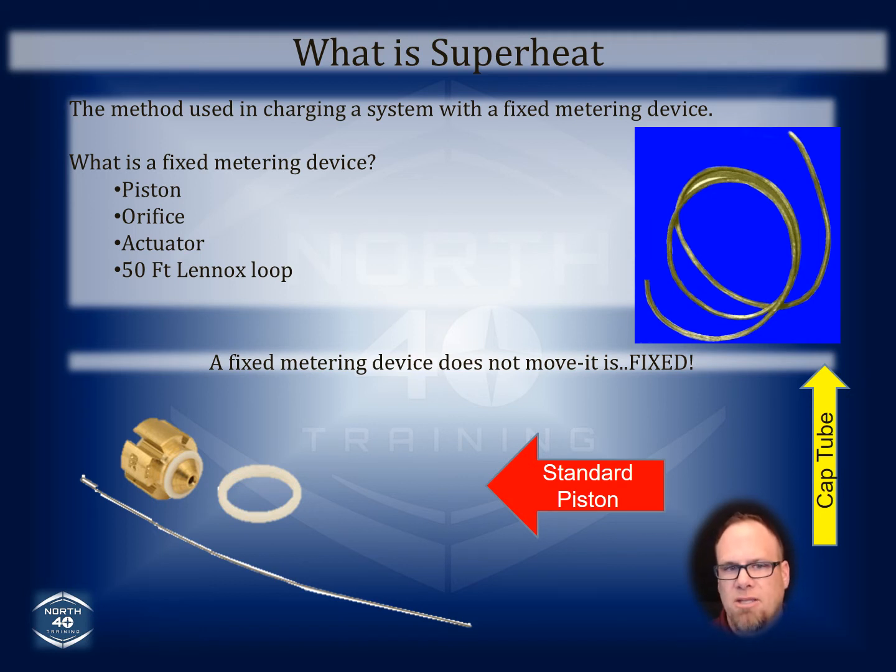We all know that water will boil at roughly 212 degrees. Okay, so it changes states at 212 degrees. We've got water, we've got steam. And on the other side, say at 215 degrees, we have steam. So between 212 and 215, the point at which it changed to steam and the temperature that it currently resides at would be superheat. We added heat to it beyond that change of state, right? So you would have 3 degrees of superheat.